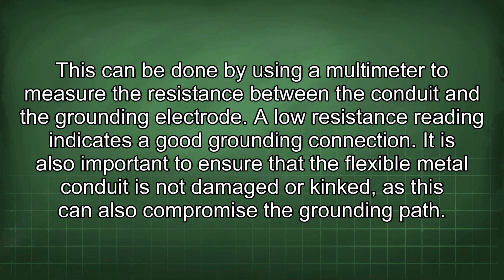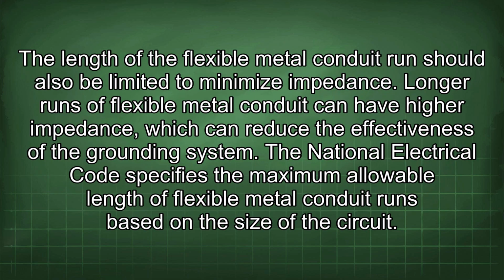It is also important to ensure that the flexible metal conduit is not damaged or kinked, as this can also compromise the grounding path. The length of the flexible metal conduit run should also be limited to minimize impedance. Longer runs of flexible metal conduit can have higher impedance, which can reduce the effectiveness of the grounding system.